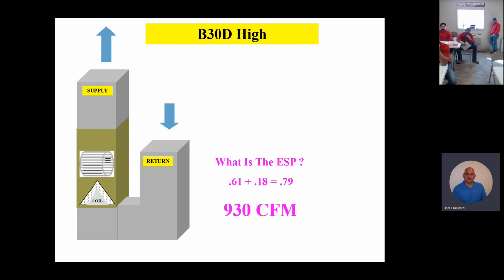So the return looks like it's nice and open, but on the supply side, even though we're blowing the CFM, as you guys can see, the static pressure is pretty high. And look at your chart again, you're going to notice the wattage is pretty high too, isn't it? Yep. And so this blower is working really hard to overcome that duct static on the supply side.